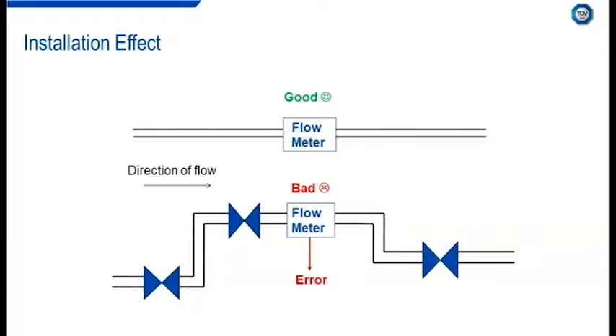So for many metering technologies, the importance of avoiding disturbances immediately upstream and downstream of the meter cannot be overlooked. Large measurement errors can be expected due to installation effects and a disturbed or skewed flow profile through the meter. As I said, the impact of installation effects on metering technologies is different depending on the meter that has actually been selected and installed. Some metering technologies are more affected by installation effects and flow profile disturbances than others, and we will discuss that a bit further when we look at some examples of flow metering technology that is available.